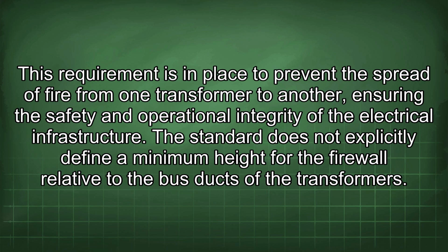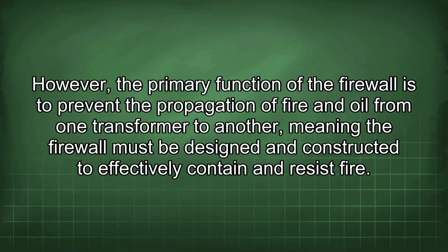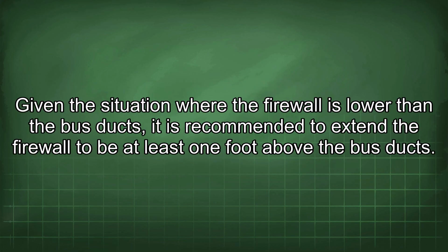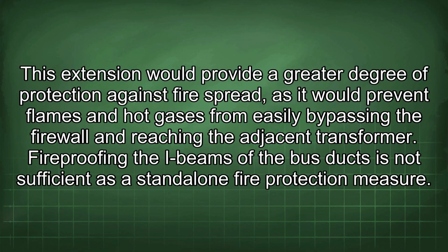The standard does not explicitly define a minimum height for the firewall relative to the bus ducts of the transformers. However, the primary function of the firewall is to prevent the propagation of fire and oil from one transformer to another, meaning the firewall must be designed and constructed to effectively contain and resist fire. Given the situation where the firewall is lower than the bus ducts, it is recommended to extend the firewall to be at least 1 foot above the bus ducts. This extension would provide a greater degree of protection against fire spread, as it would prevent flames and hot gases from easily bypassing the firewall and reaching the adjacent transformer.